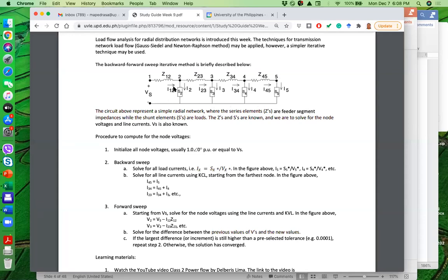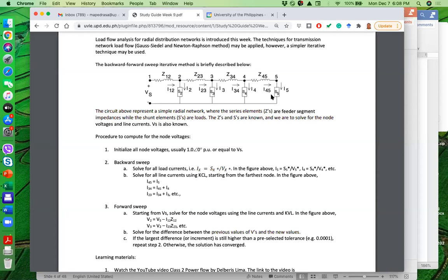The first step is to initialize all node voltages. For this network, what we know are the line impedances: Z12, Z23, Z34, Z45 — all are given. Vs is also given, usually one angle zero, which is the substation voltage regulated at that point. The other given values are the complex power drawn by the loads: S2, S3, S4, and S5.